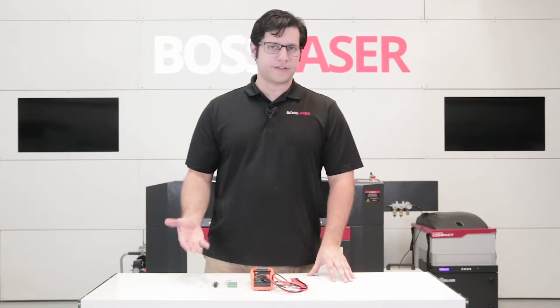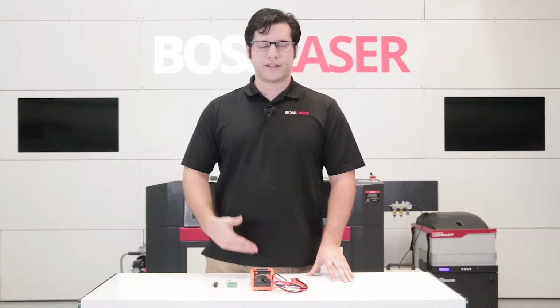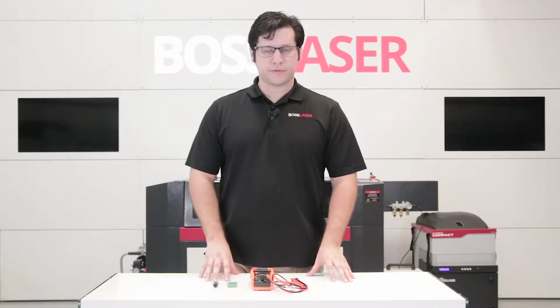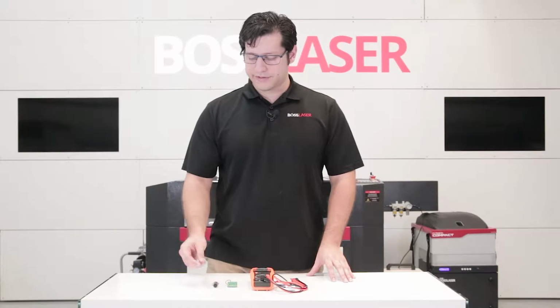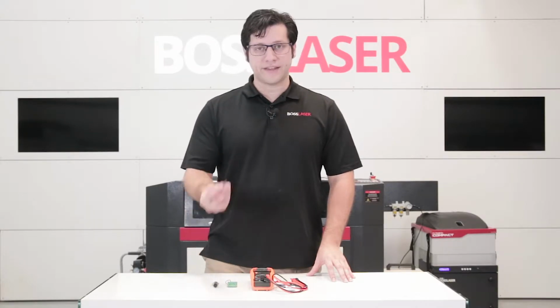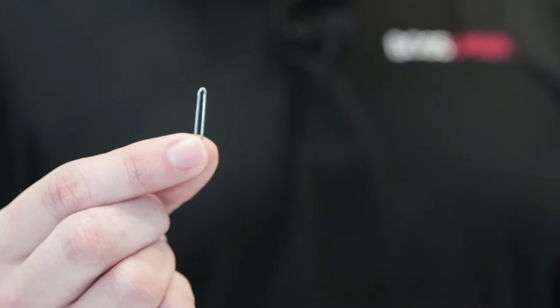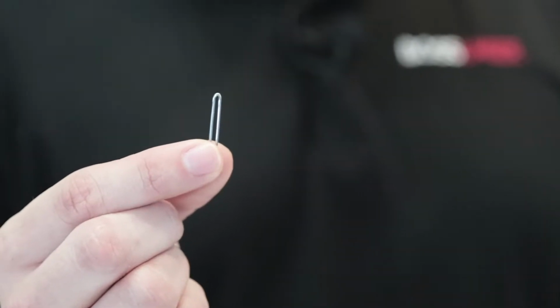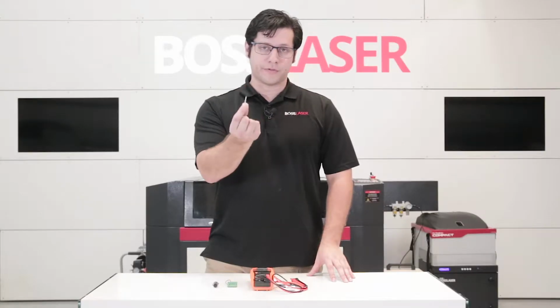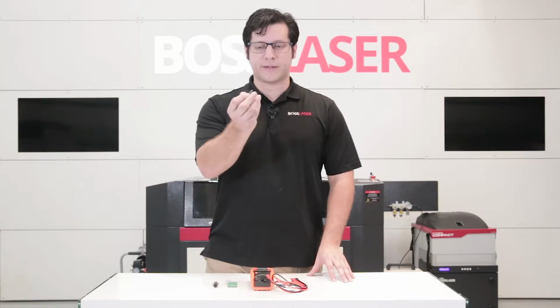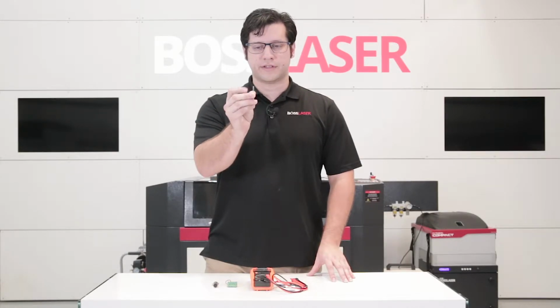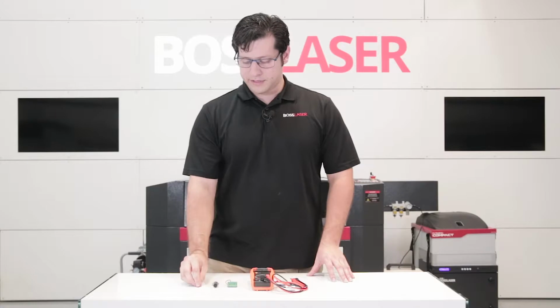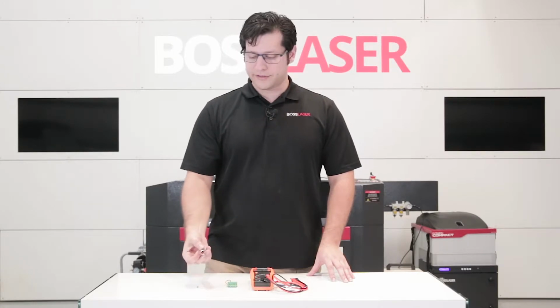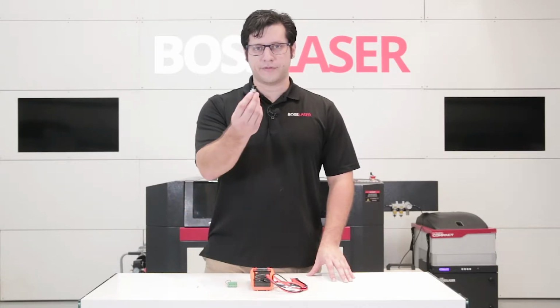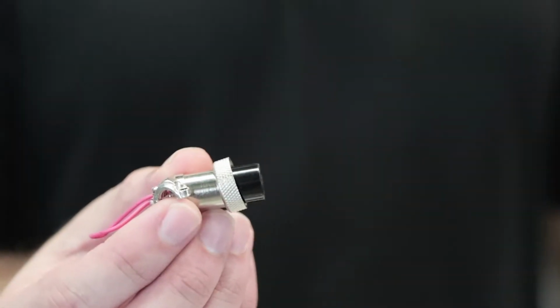The tools that you're going to need to check your interlocks on the laser machine, you're going to need 4 in total. The first tool that we're going to list here is actually a pin that you could create, that you can use for your door interlock and your water flow sensor. So we're going to need a type of pin that you can fashion out of a paper clip. And then, included in your toolbox, is a chiller bypass. So this is for the connection in the back where your chiller cable goes.